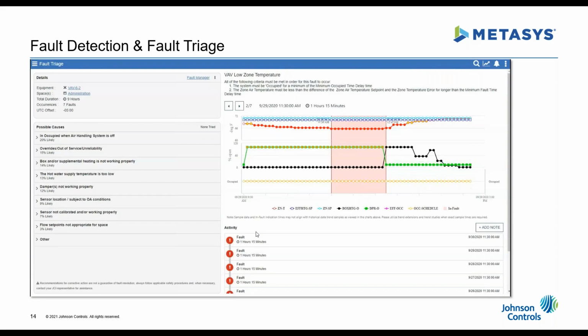So with fault detection, we get into the actual types of faults that we can see here. So here we've got a VAV low zone temperature fault. And you can see some of the criteria that are set up for that. So the system must be occupied for a minimum amount of time. The zone air temperature must be less than the differential between the set point and the error. So a whole number of different trends come into this particular fault. And this is something certainly no human is going to have the time to look at on a regular basis, but the system, the BAS, can look at this 24 hours a day and determine when these faults occur. And it can show us how many of these faults have occurred over time, and start giving us a prioritized list of what is the most severe fault in the building, or really a prioritized list of faults by severity, if you will. So if we can move on to the next.